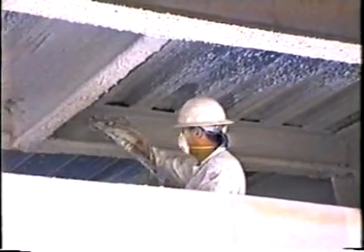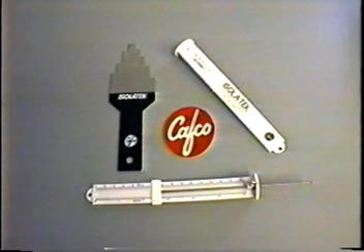This should be repeated on both sides before finishing with the outside flange. Thickness checks should be randomly taken in order to ensure that the sprayer doesn't exceed the required design thickness. The following are recommended thickness gauges for CAFCO wet mix materials. Excessive thickness may result in delamination or prolonged drying time and is the most common reason for reduced yield.